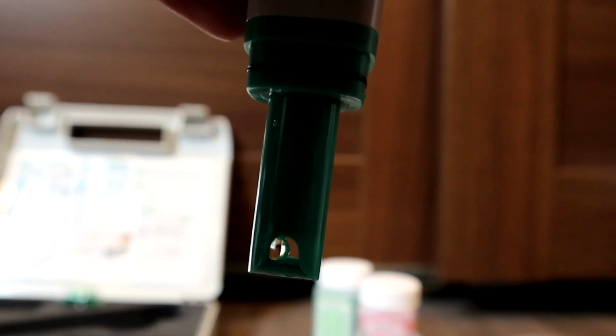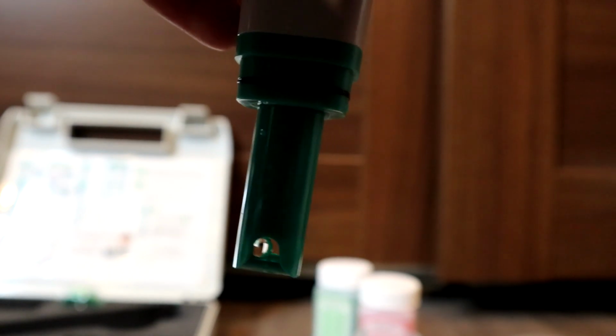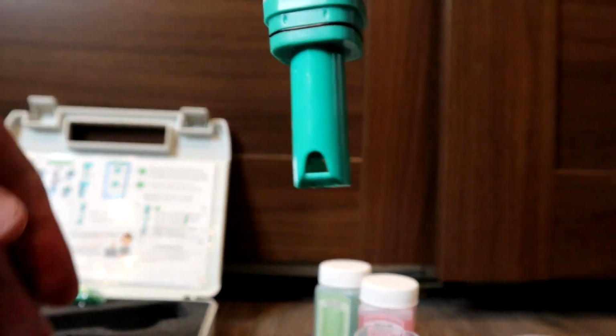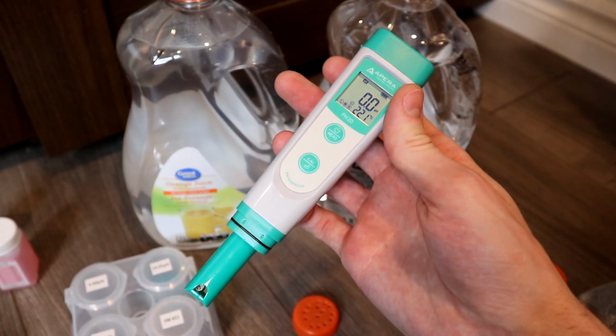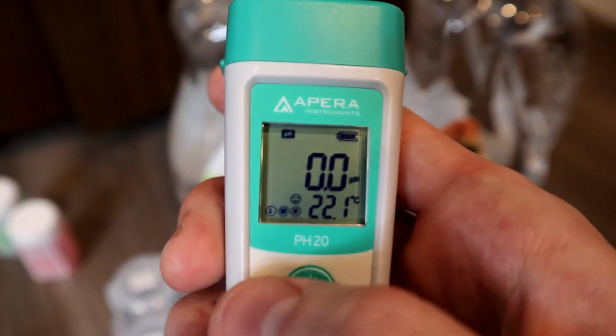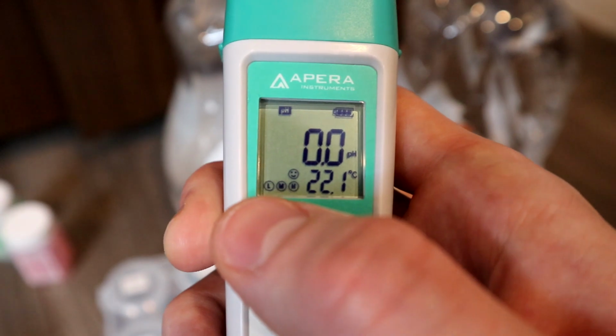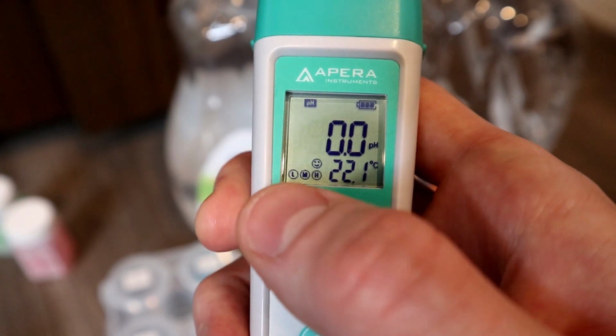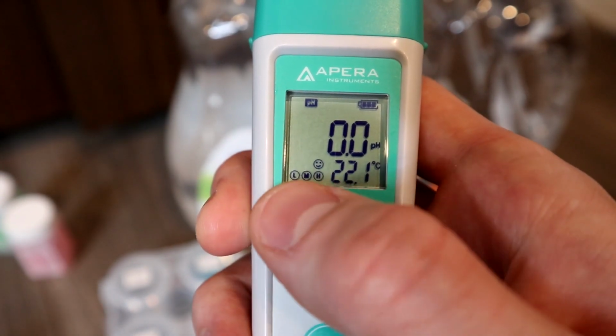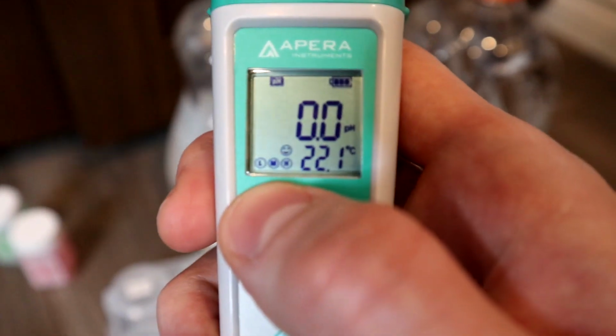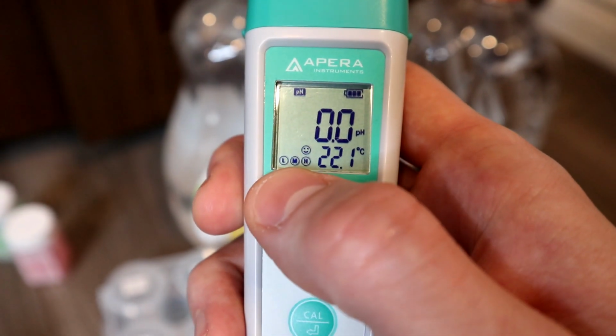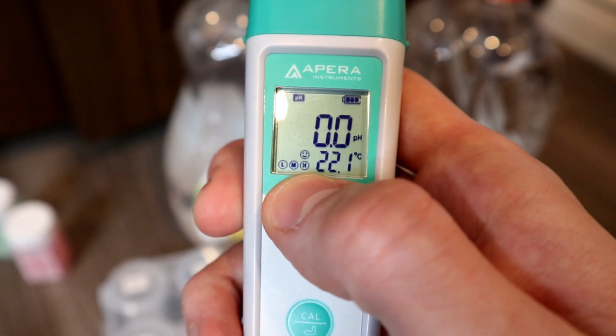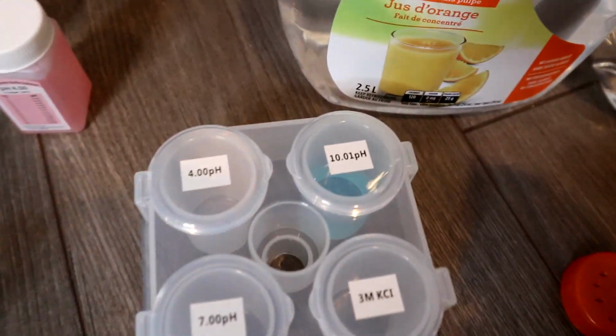I took it out and gave it a good, pretty violent shake. Just make sure you have a good grip on the probe. And that got rid of the air bubble. So I've already calibrated the meter here just to make the video a little faster. And you can see there's an L, an M, and an H down there, low, medium, and high. That's showing that I've calibrated it 3 points. So the low would be the 4 pH, medium is 7, H there for high is the 10.01.